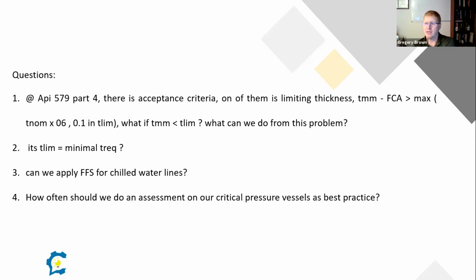For piping in the current version, that 1/10 of an inch requirement has actually been relaxed to 0.05, because there's thin wall piping. So if you don't meet that requirement, really your only option is to do a level 3 analysis to have some reason why you could operate that equipment when you're below that limiting thickness.